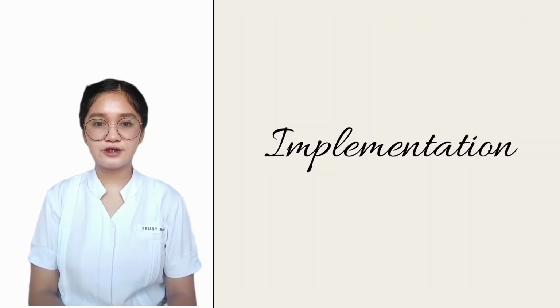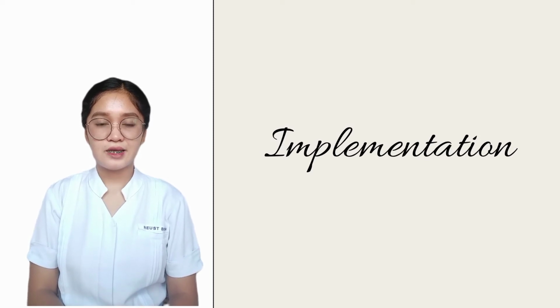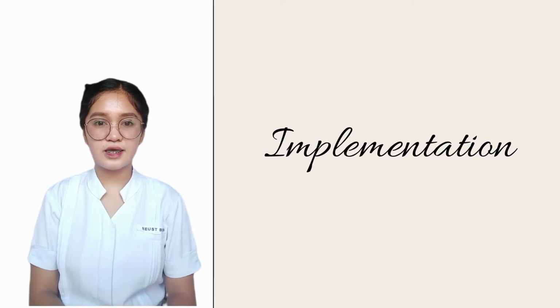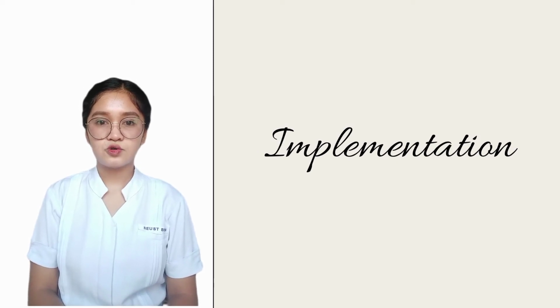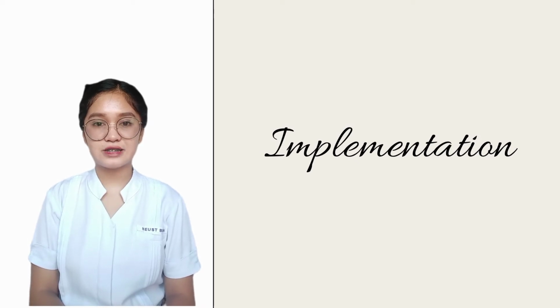Remove sensor on a regular basis and check for skin irritation or signs of pressure every 2 hours per spring tension sensor, or every 4 hours per adhesive finger or toe sensor to check for irritation.